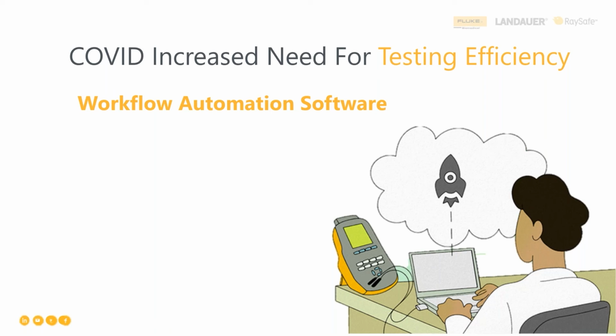But if it failed, then we also need the failure information in order to populate in the database a series of entries that allow us to trend over time and get a failure rate. So workflow automation is what helps us do that. And those of you that have a CMMS that you interact with in real time, and then if you're not online during that real time work, it will automatically synchronize and upload your results to your work assignment to help you close it.